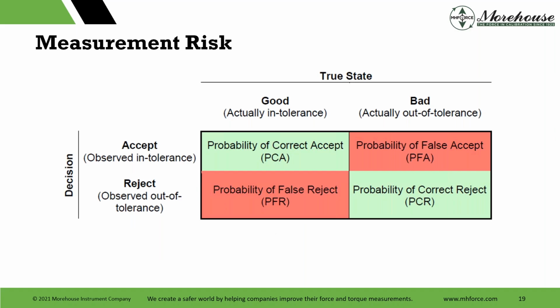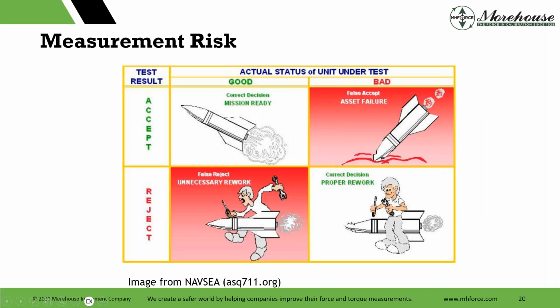And again, if you want to download our decision rules book, it's available online. This is good, bad, probability of false accept, reject probability. The Navy has one of my favorite slides, which basically says, hey, false accept, we have asset failure. We have a rocket or missile not hitting where it should be hitting, the right targeting system. And if we have a false reject, we're working on things we should not be working on.